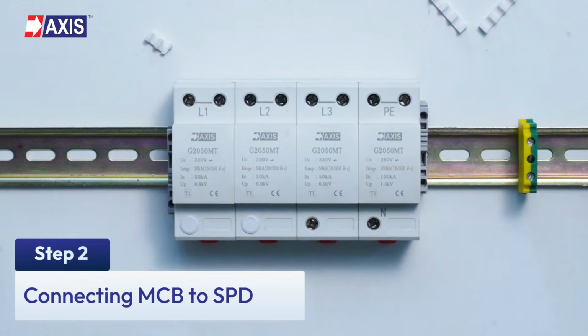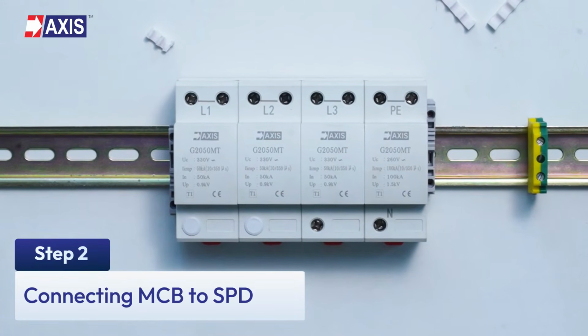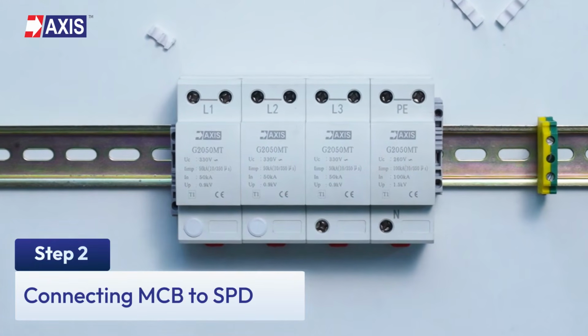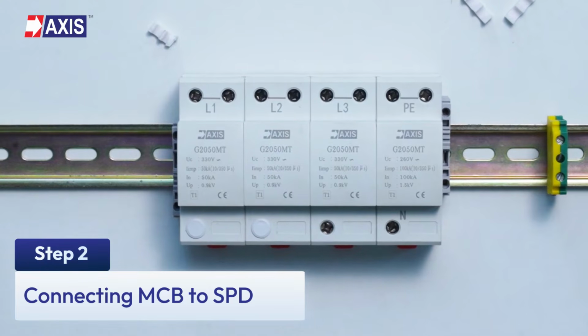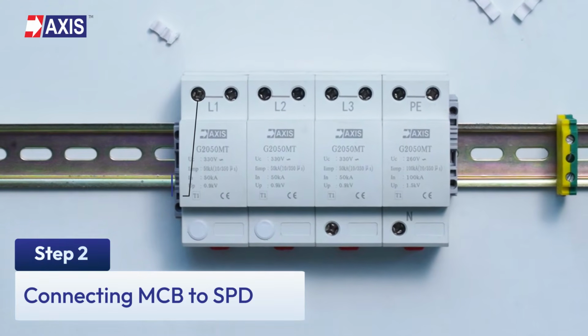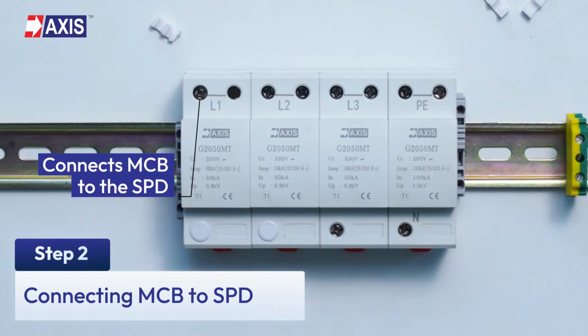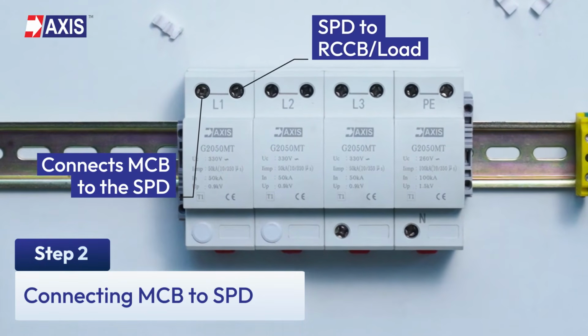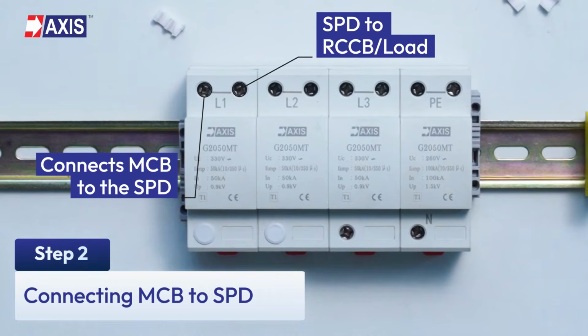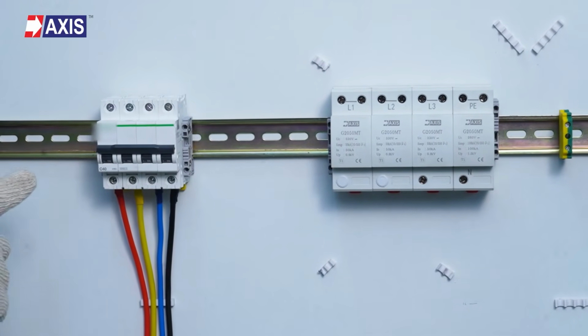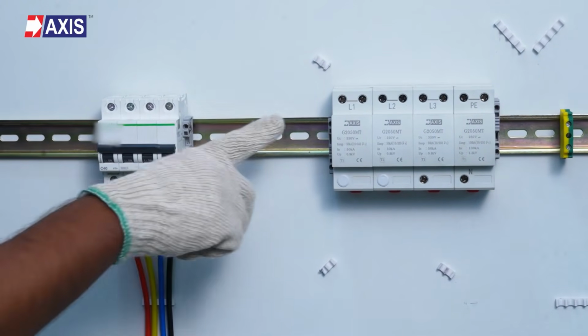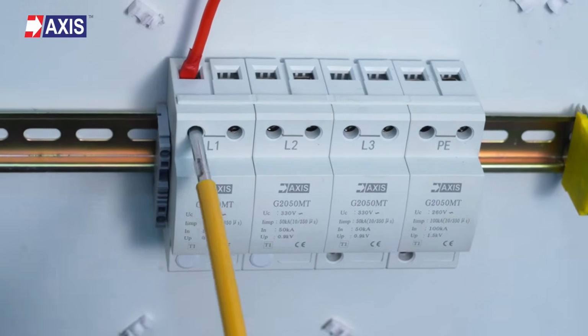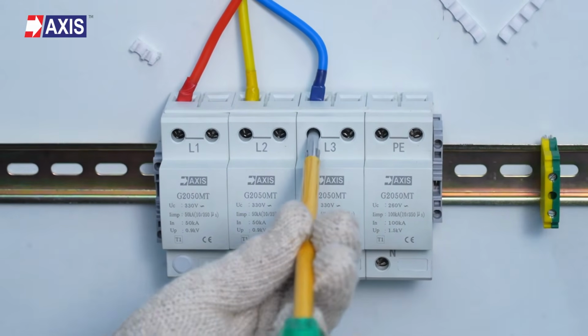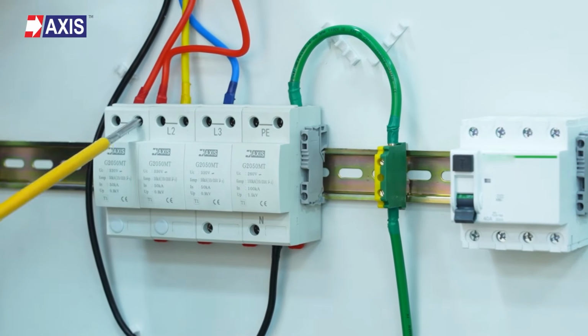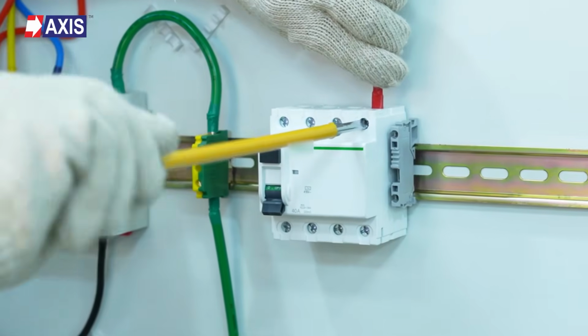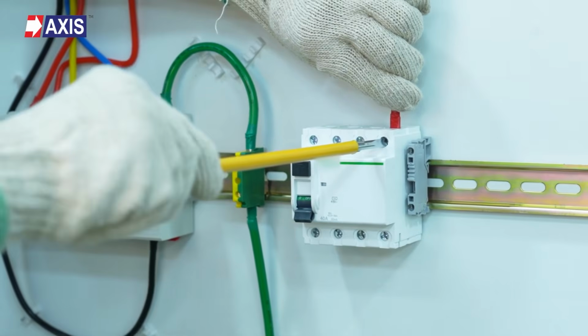Step 2. Connecting the MCB to the SPD. For the Type 1 SPD, the SPD has two terminals for the V connection. One terminal connects the MCB to the SPD and the other connects the SPD to the RCCB or the load. Start by taking a connection from the output terminals of the MCB and connect each of the corresponding input terminals on the SPD. Then connect the second terminal of the SPD to the RCCB or directly to the load.